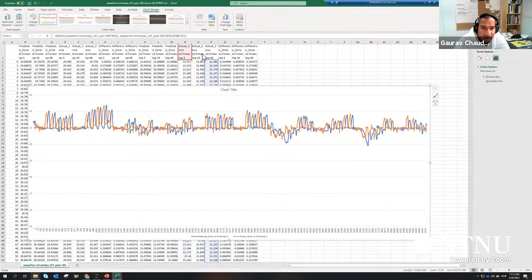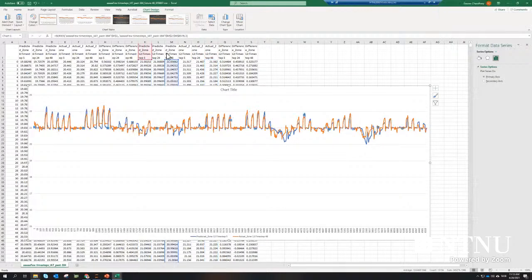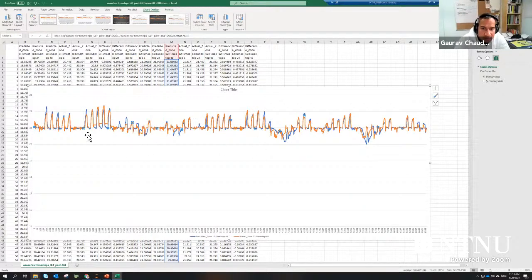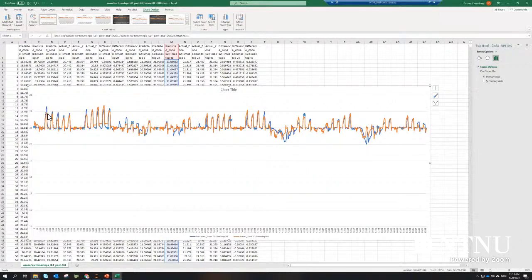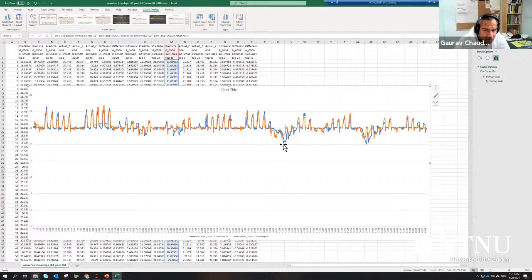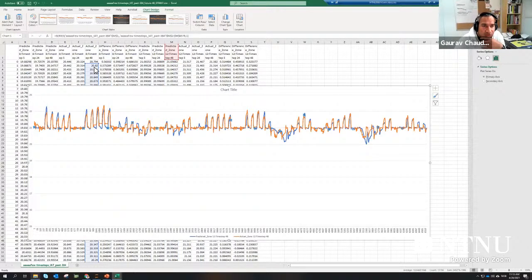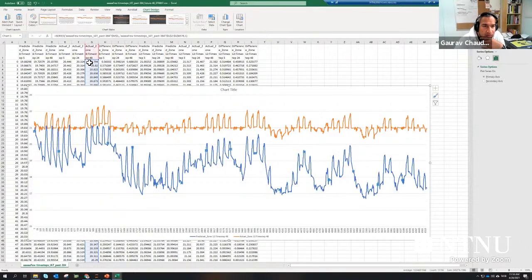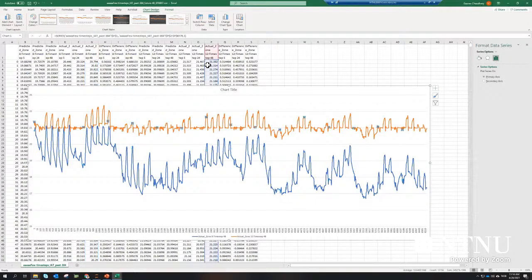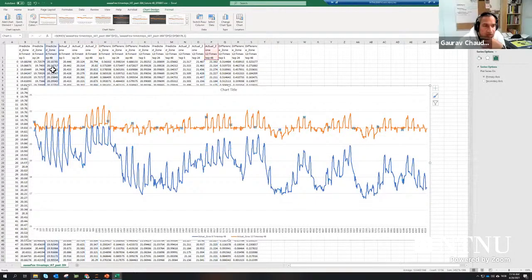If I try to see how it was with the 48-hour prediction, 48 time steps, which was 12 hours ahead, there we see that it's able to capture the overall peaks within half a degree range, but then it falls short when suddenly there are drops in the temperature. If we see zone 12, which was much harder, for the next 48 time steps, we can see that.